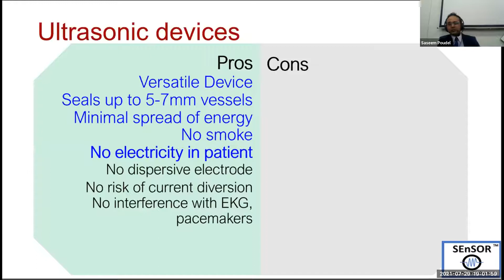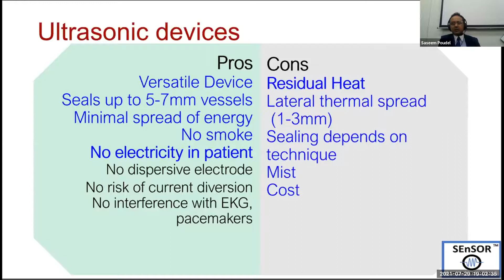On the other hand, the biggest drawback of these devices is that they have a very high residual heat. Lateral thermal spread depends on the setting you use, but there is a lateral thermal spread of 1 to 3 millimeters, and sealing quality depends on the technique that you use. There is mist formation that often blurs the vision, and obviously it is more expensive than your normal monopolar devices.